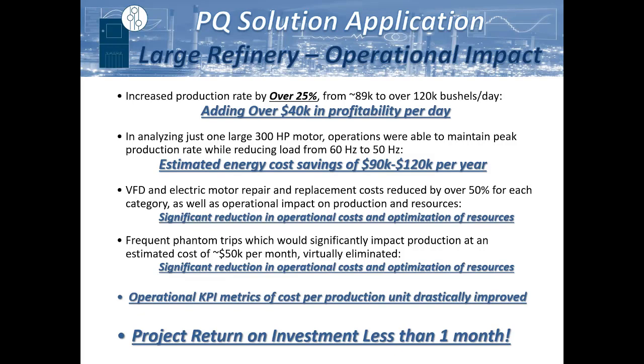They also noticed they could look at individual motors, like this one 300 horsepower motor that was on a VFD. The VFD was really only there for startup conditions, but they realized they could maintain the same rate and reduce the speed on that motor from 60 hertz to 50 hertz. That was about $100,000 in electrical savings right there. And I've also kind of downplayed this a little bit.